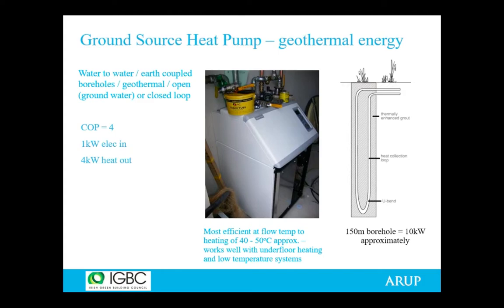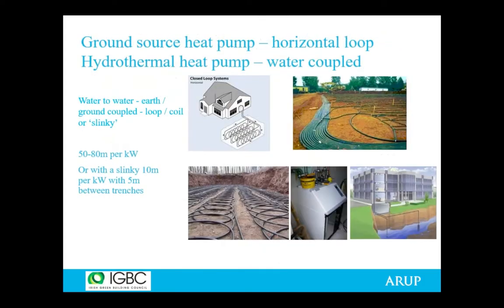There are different types of heat pumps. The one shown on this slide is a geothermal heat pump, which takes heat from the ground through a closed loop borehole sunk into the ground. The boreholes tend to be about 150 metres deep, and you can need quite a significant number of them to deliver energy to a large scale building, because you get on average about 10 kilowatts, depending on ground conditions, out of a 150 metre deep borehole — so that's quite a lot of drilling for quite a small amount of heat energy.